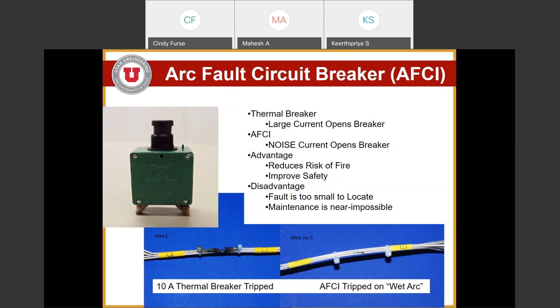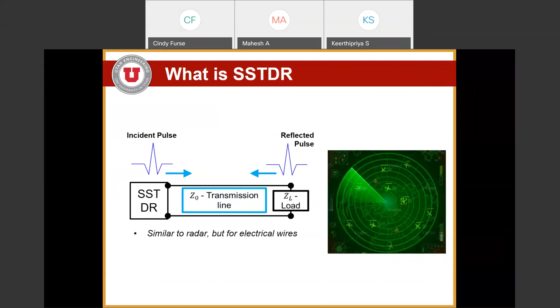So we're using a method we invented called spread spectrum time domain reflectometry. It's kind of like radar, but for electrical wires. An incident pulse is sent down the transmission line and a reflected pulse comes back—that's standard reflectometry. The delay between the pulses tells you where the fault is, and the type of pulse, whether it's positive or negative, tells you if it's an open or a short.